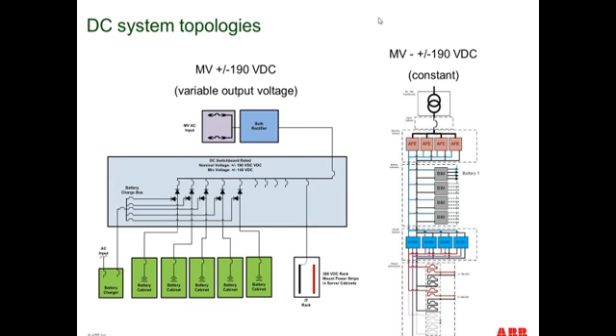Number of benefits to having that additional conversion. One is we have a constant voltage system that enables us to build a much smaller infrastructure. Another is we're electronically limiting the battery energy through the DC to DC converter, so issues like high short circuit currents and arc flash that people either don't understand or are afraid of become non-issues in this type of topology. So all of these systems that are modular in nature really go back to and take a lead from, in some way, shape, or form, a 48-volt topology.